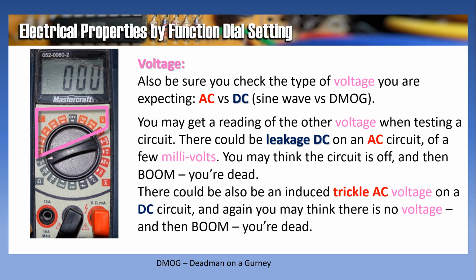You may get a reading of the other voltage when testing a circuit. There could be leakage DC on an AC circuit of a few millivolts. You may think the circuit is off, and then, boom, you're dead. There could also be an induced trickle AC voltage on a DC circuit. And again, you might think there's no voltage, and then, boom, you're dead.